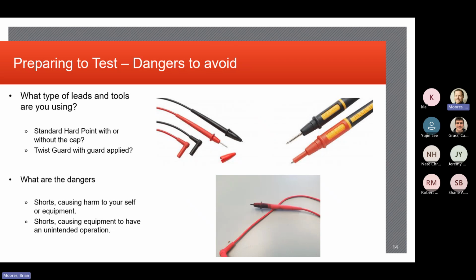I've physically been burnt by an arc flash. It's hot. That's all I can tell you, it's very, very hot. So we've got to be mindful of the equipment that you use. It's in good condition. You've got the barriers, like this little twist guard plug on the upper right hand side. You can see the black lead has its barrier retracted, and then the red lead has it pushed forward. So you don't touch those two leads together if you're too close to a plus or minus DC, for example. So very mindful of this.